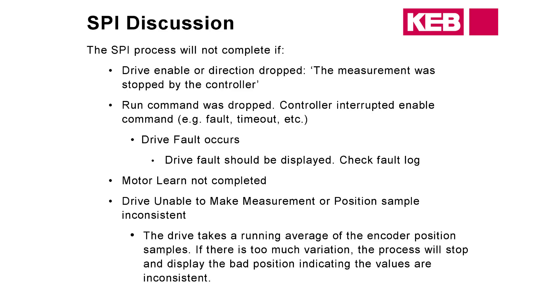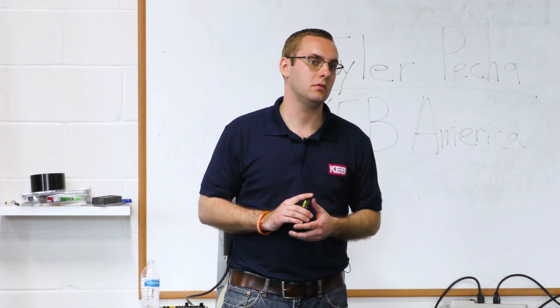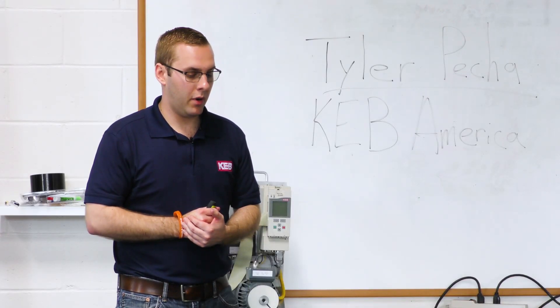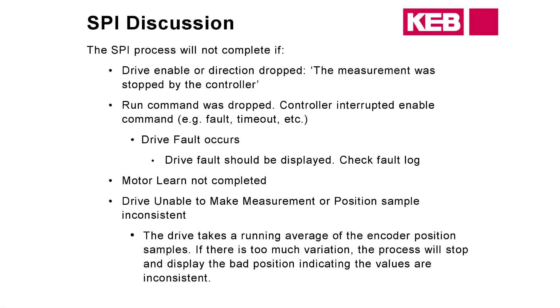A few things that could happen during the SPI. You might get an ECDD — error calculating motor data — and wonder why, since you already did the autotune. That's because the drive actually uses the motor model to calculate the encoder position. Encoder position uses motor inductance in the calculation, so if you've got bad motor data to start, it won't be able to calculate the correct encoder position. So again, motor data is something to check.